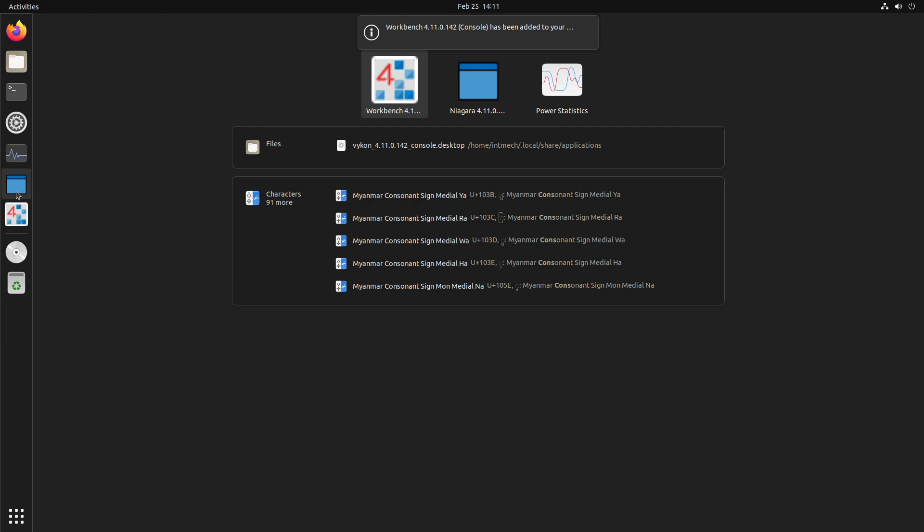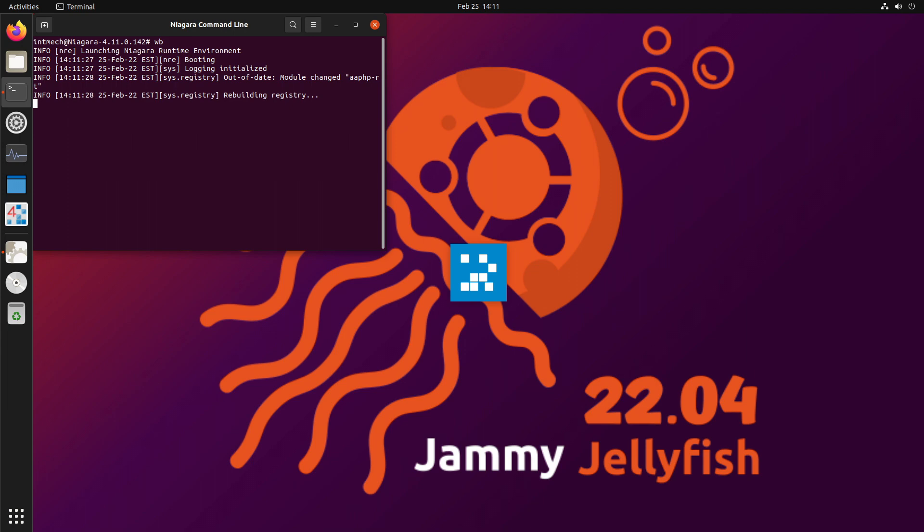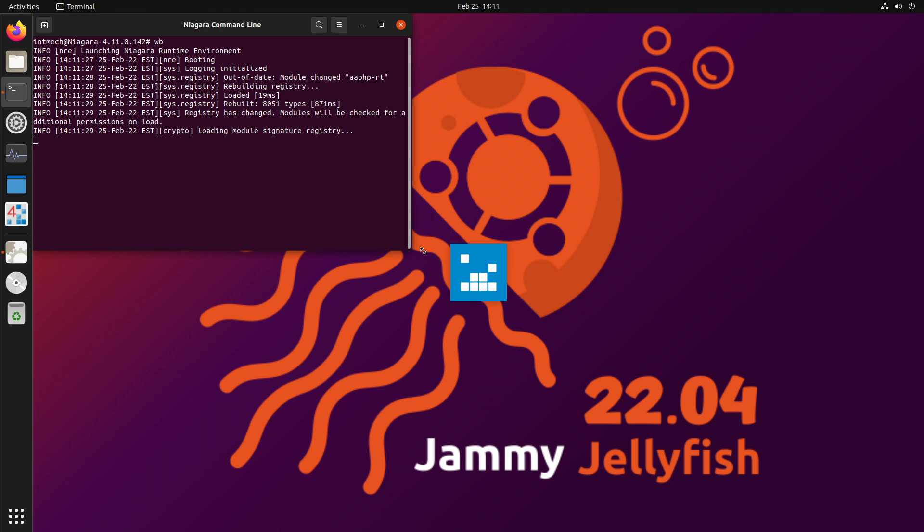And you could just launch Workbench right from here. However, I like to launch Workbench, and the Java developers that work with Niagara will tell you this, I like to launch Workbench like this. It's just WB from the Niagara console. And the reason is that if you had issues, you would see what those issues were right here in the console. It can be really handy when you're first trying to figure things out. Or forever.